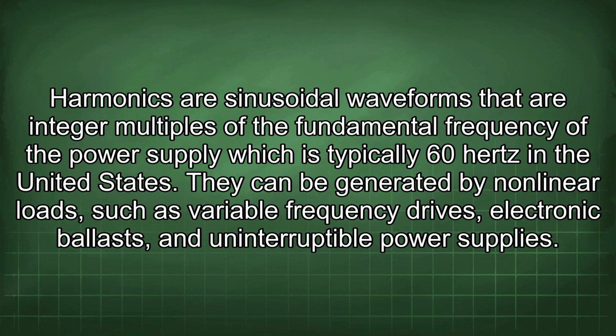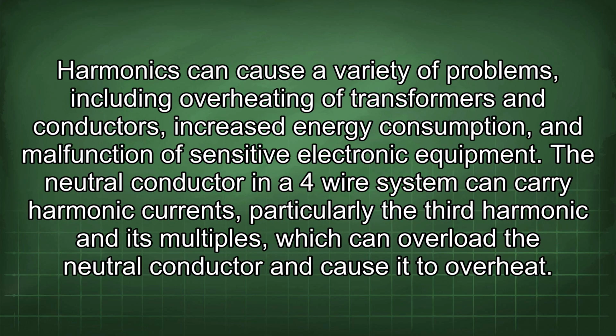Harmonics are sinusoidal waveforms that are integer multiples of the fundamental frequency of the power supply, which is typically 60 Hz in the United States. They can be generated by nonlinear loads such as variable frequency drives, electronic ballasts, and uninterruptible power supplies. Harmonics can cause a variety of problems, including overheating of transformers and conductors, increased energy consumption, and malfunction of sensitive electronic equipment. The neutral conductor in a 4-wire system can carry harmonic currents, particularly the third harmonic and its multiples, which can overload the neutral conductor and cause it to overheat.